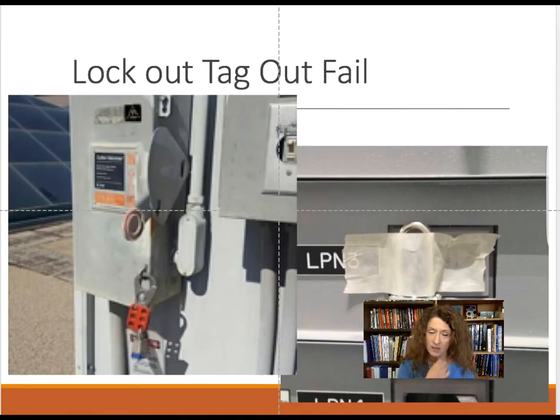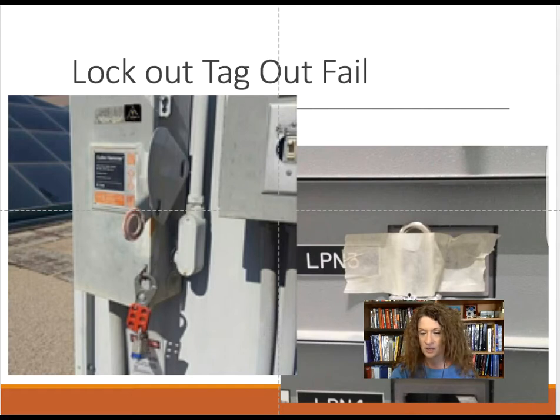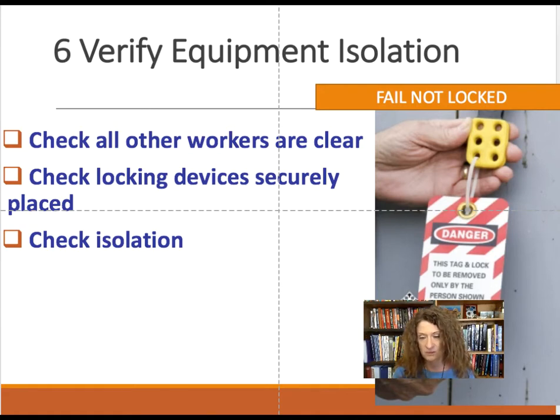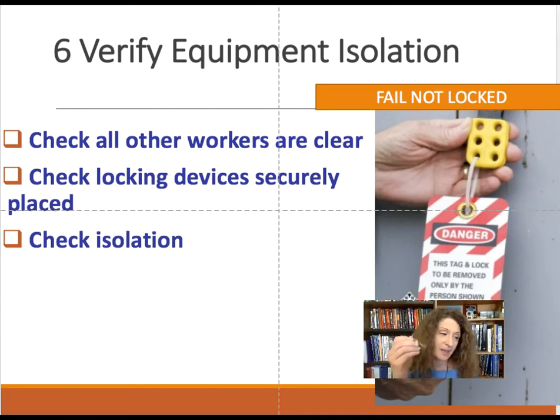Here are examples of lockout-tagout fails. In one example, they're locking out the opening of the box — but opening the box won't kill you; throwing the switch would. A piece of tape is not considered a physical barrier and can fall off. Step 6, which is sometimes forgotten, is to verify that equipment has been isolated, that workers are out of the work area, and that all energy sources are isolated. In another example of improper lockout, a tag is on the hasp which anyone can remove — you want someone to physically have to use a key to remove a lock.